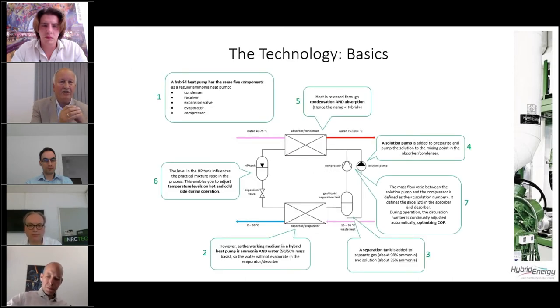In brief, the technology basis, there are four main components. It's the condenser, it's the expansion valve, it's the evaporator, and it's the compressor. What makes a hybrid pump special is that there is a gas liquid separation tank, and the gas is of course handled by the compressor. The liquid mixture is handled by the solution pump. And the large benefits, as mentioned, is that we can achieve very high temperatures working at moderate pressures and with better operational conditions for all machinery equipment.